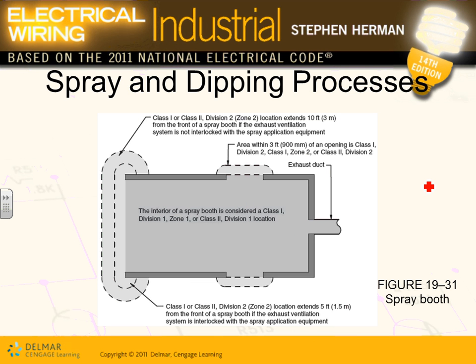This is a spray booth. Do you guys remember when we went to Cummins and EMI? They have a spray booth. Inside your spray booth, there could be a class 1 or class 2 location, div 1. That's where they're spraying. There could be flammable gases and ignitable dust. Both exist in that area. And there's also the zone. If you hear the word zone, zone 1, guys, is equivalent to div 1. Zone 2 is div 2.